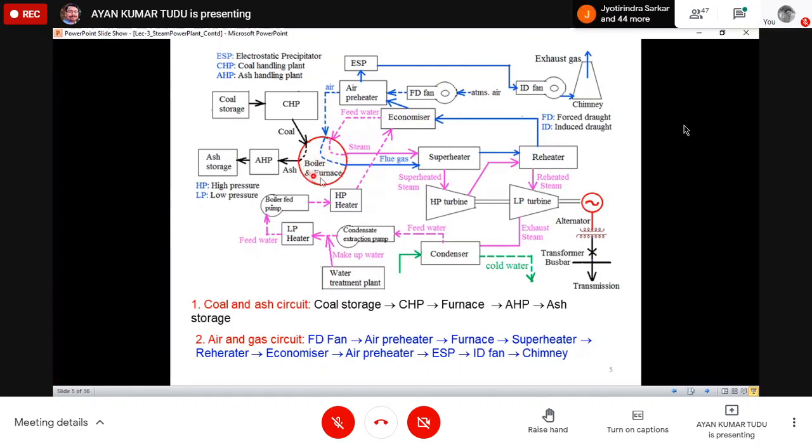Okay, and in the boiler drum and the boiler tubes, the water will be circulating due to convection current. Now what about the steam? As you can see, the wet steam passes through the separators in the boiler drum to separate water droplets from steam. The steam is further heated in the superheater before being supplied to the high pressure area of the turbine.